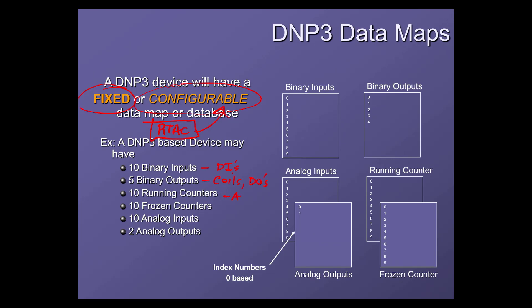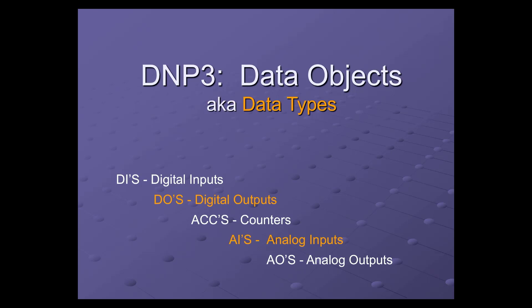When it comes to a DNP3 device, it can have any or all of the different data types found in your object library. In the object library, binary inputs are DIs — digital inputs. Binary outputs are what Modbus would call its coils or DOs. Then you have your counters or accumulators, frozen counters, analog inputs, setpoints or analog outputs, and so on. Even though these objects have different names in the data map, they're essentially all data types you're familiar with — just different names, plus additional functionality like frozen data types or event data types.